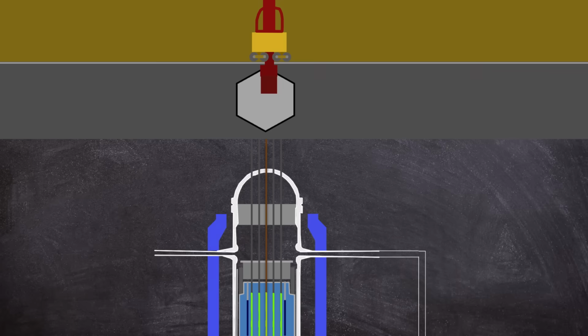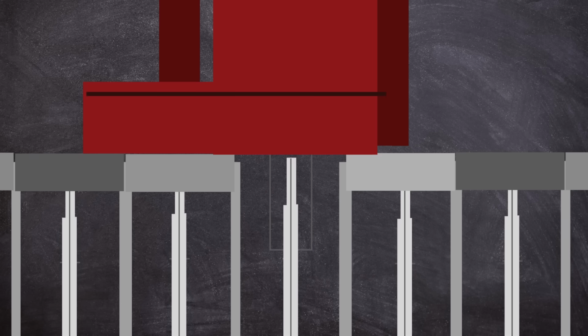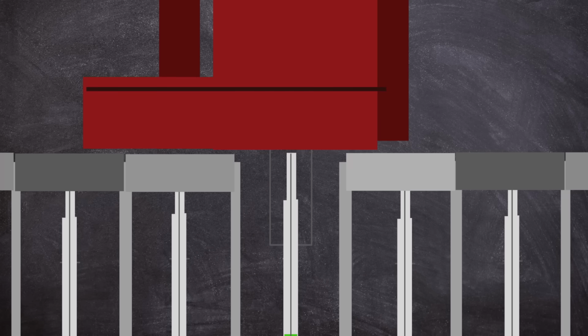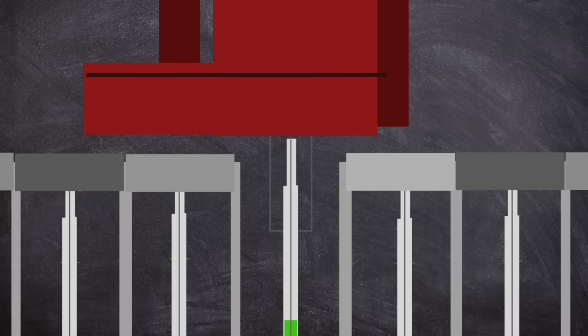The spent fuel rod was extracted from the core into the refueling machine, after which the tightness of the plug at the top of the reactor was checked. The spent fuel was then moved off to the spent fuel area, and this was at around 11:55 in the morning. The refueling machine then went to insert a new rod. After apparently being sealed, which was indicated to operators by an electrical indication, the refueling machine began to lift away as per the operating instructions.